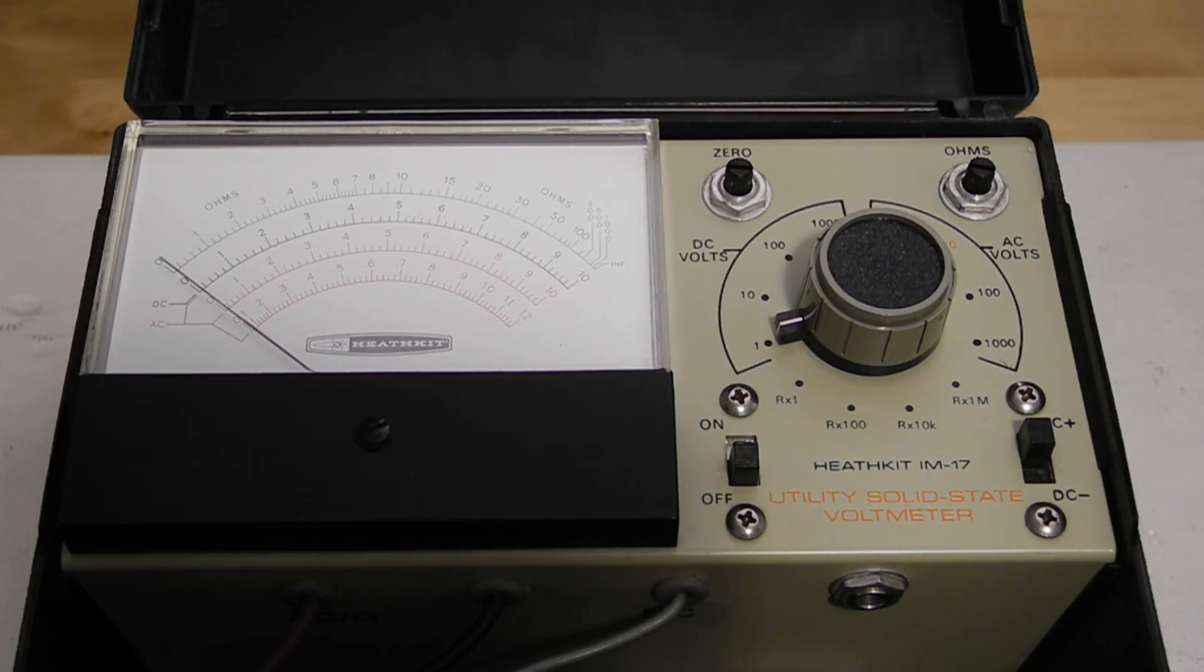The zero knob is adjusted so the meter reads zero with no input. This needs to be set from time to time due to temperature changes or as battery voltage varies.